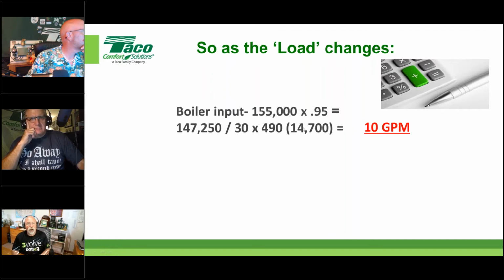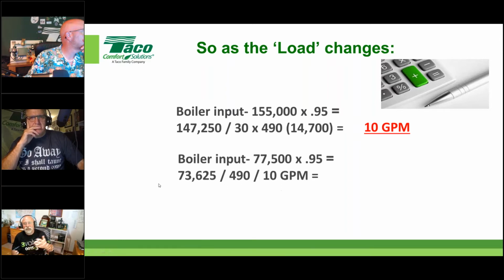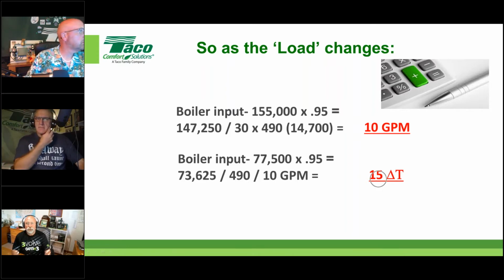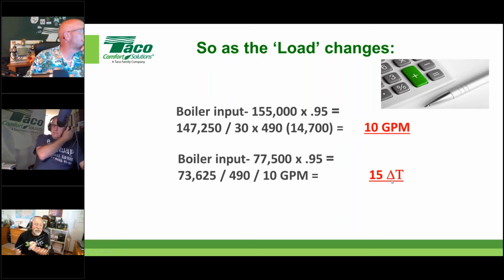What happens when we're not running at a design load condition? Let's just cut it in half. And for the sake of time, I'm going to do the same math for you and do the division by the given GPM to find out what the resultant delta T is. Okay, so that means at half load, I'm going to drop from my 30 that I used at a design condition to half of that, which is a 15-degree delta T. It's not as good, but it's a lot better than the guy that wagged and put a 15-gallon a minute pump in there.